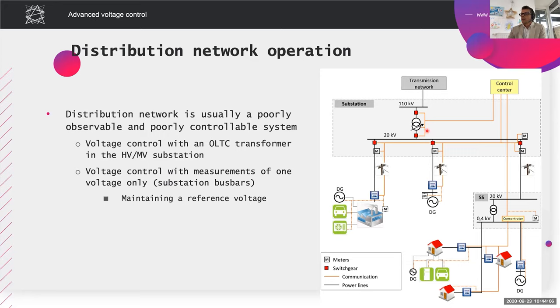This tap changer measures the voltage here at the secondary busbars and adjusts this voltage according to a reference value. So it's very simple. If you increase the voltage with this transformer, the voltage in the whole network is increased. If you decrease the voltage with this transformer, the voltage in the whole network is decreased. So it's a very simple way of controlling the voltage.